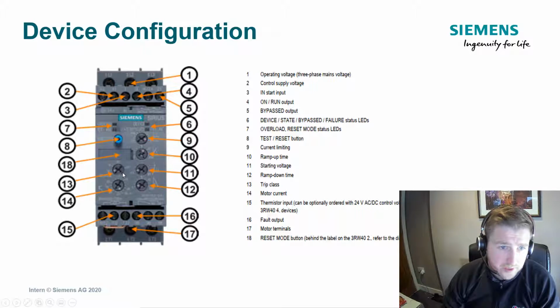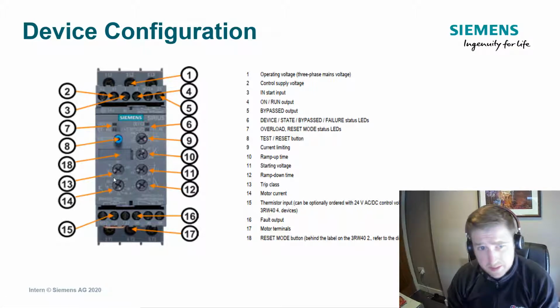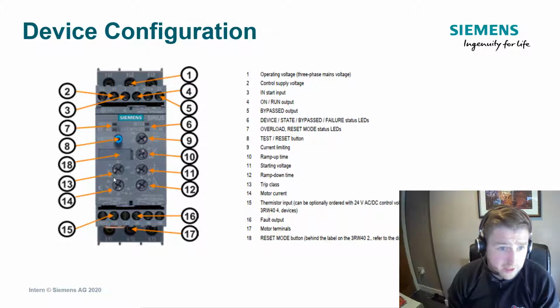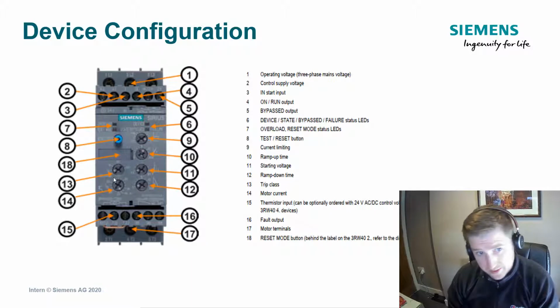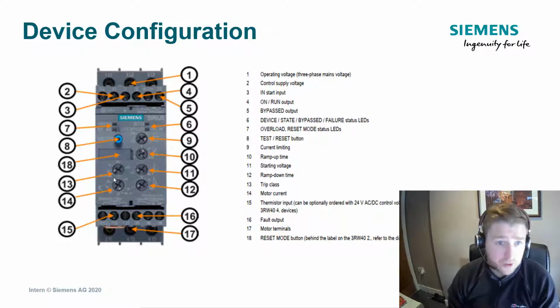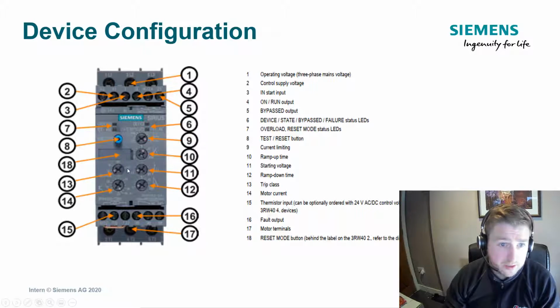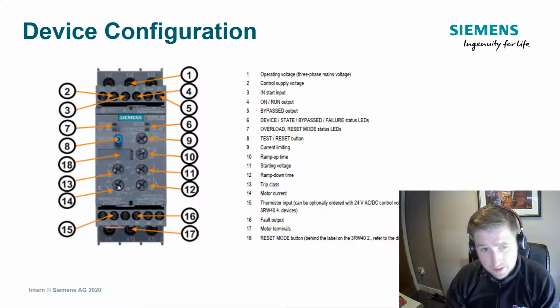The first one at the top, labeled number 13 and covered by this orange arrow, says class, and you can decide. This device has a built-in overload, so there's class 10, 15 and 20. Class 10 is a startup of up to 10 seconds on the overload. If you have a 15-second startup, use class 15, and if you have just under 20, use class 20. Or if you don't want to use the overload function, you have the ability to turn that off. This pot here, number 14, is the motor's current rating. On the nameplate of the motor, it'll show the general operating current of that motor, and that's what you set that potentiometer to.